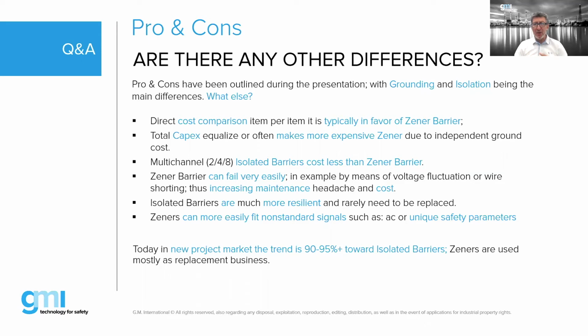And we talked about the isolation of the sensor, Bob, in the presentation. I don't remember if we really talked about it. When you say isolation of the sensor, you mean the field device that the barrier is connected to. If it is a Zener barrier, 500 volts of isolation is required. You cannot ground, for example, a thermocouple; you have to ensure that there is isolation in the field. You have grounding in the control room and isolation in the field. Whereas with an isolated barrier, you don't need the grounding, and at the same time, you could have a grounded sensor. You don't have to worry about the grounded sensor.